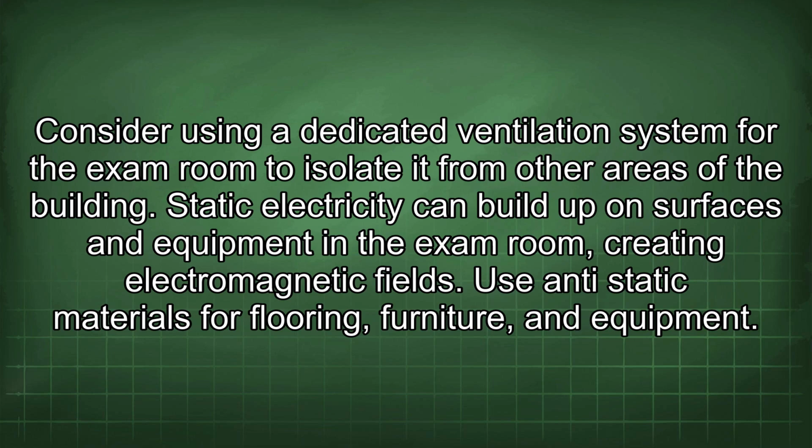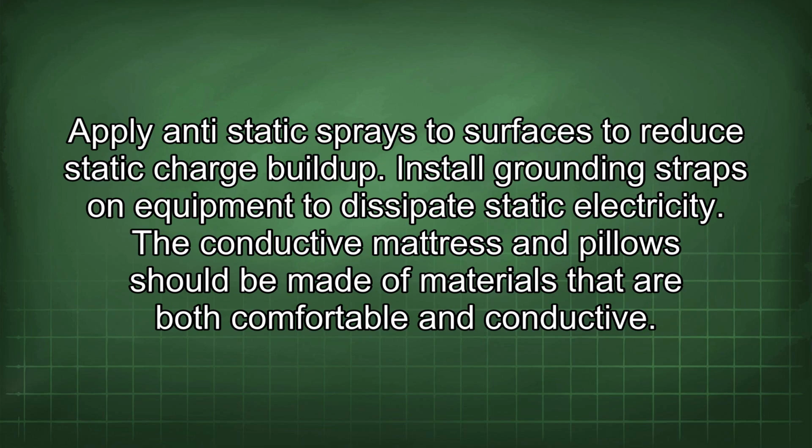Static electricity can build up on surfaces and equipment in the exam room, creating electromagnetic fields. Use anti-static materials for flooring, furniture, and equipment. Apply anti-static sprays to surfaces to reduce static charge buildup. Install grounding straps on equipment to dissipate static electricity.